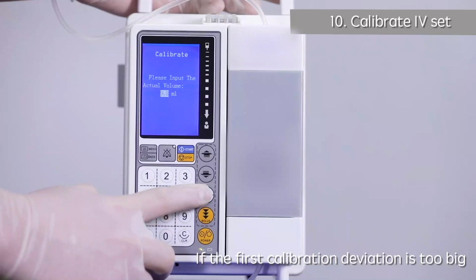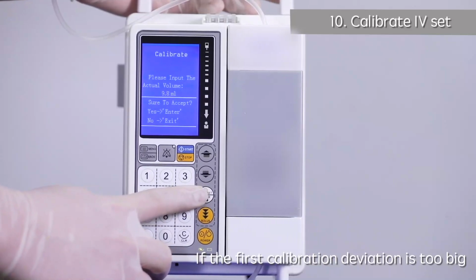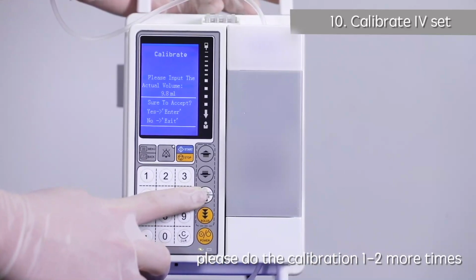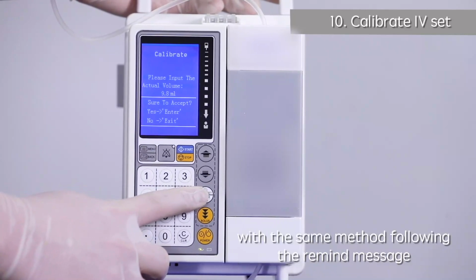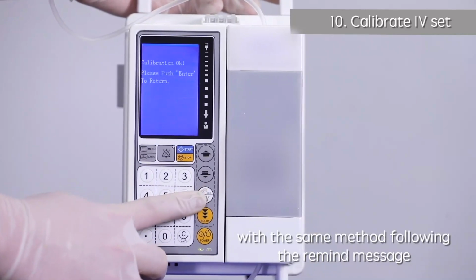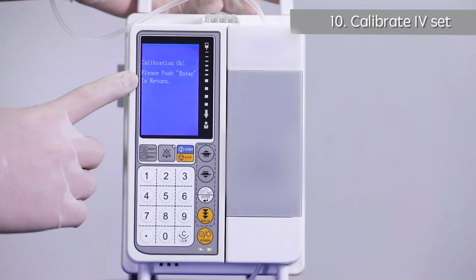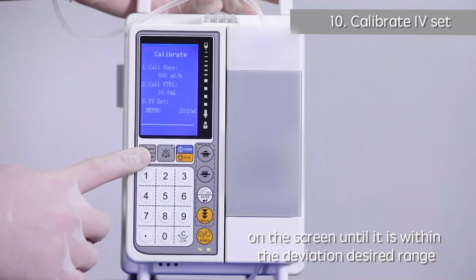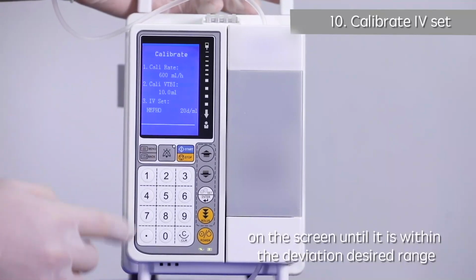If the first calibration deviation is too big, please do the calibration 1 to 2 more times with the same method, following the reminder message on the screen, until it is within the desired deviation range.